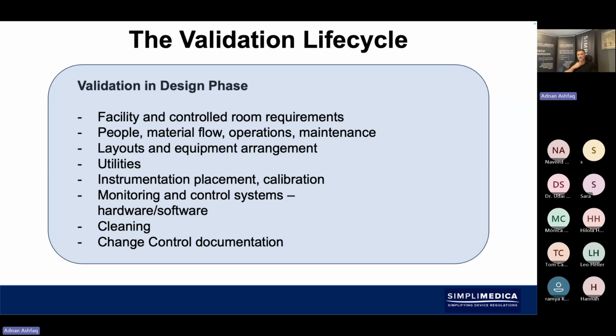Validation in the design phase also allows for facility and controlled room requirements. So if you're manufacturing a sterile device, the equipment that you're validating could be sterile packaging. We also need to look at the control of the room: does it need to be in a clean room, and what classification of clean room, etc. So these are all important external aspects to look at from validation, which is not only looking at the equipment itself, but also the environment where the equipment would be residing.